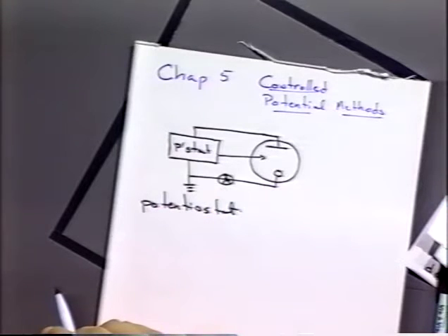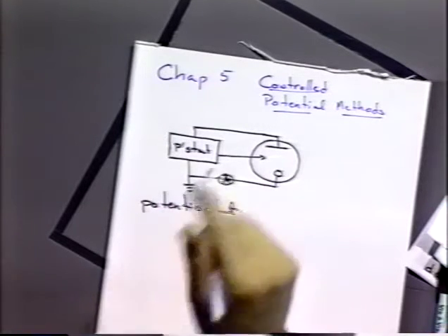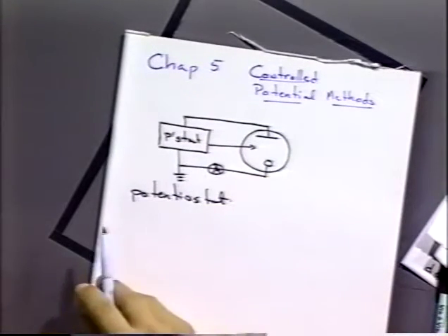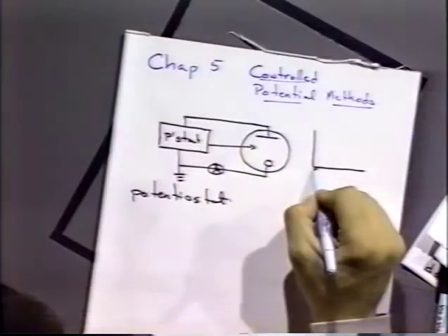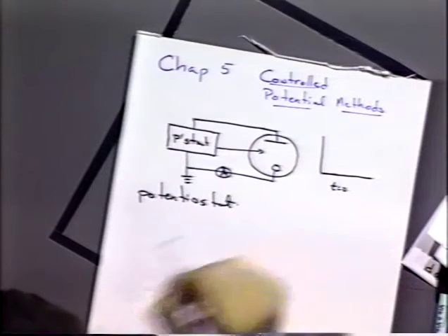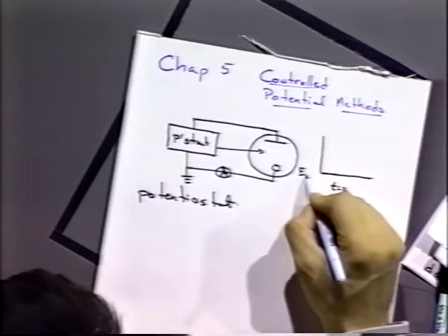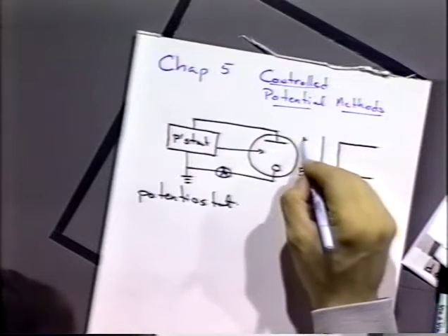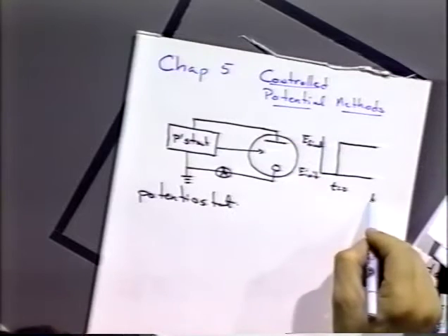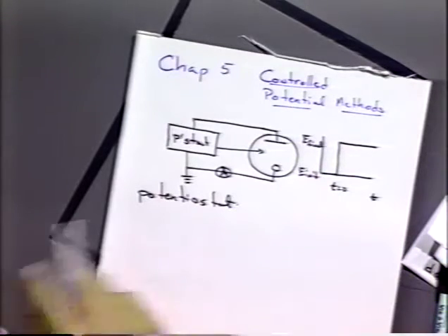We have in there some sort of a current meter to measure the current. The potentiostat has the ability to hold a potential constant, and it also has inputs so that we can control the voltage applied — either by applying a voltage sweep, commonly a voltage step, or a voltage pulse. A typical experiment starts at some initial potential at time zero and steps to a final potential.